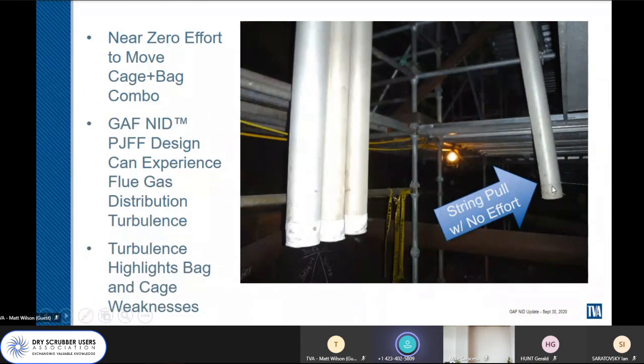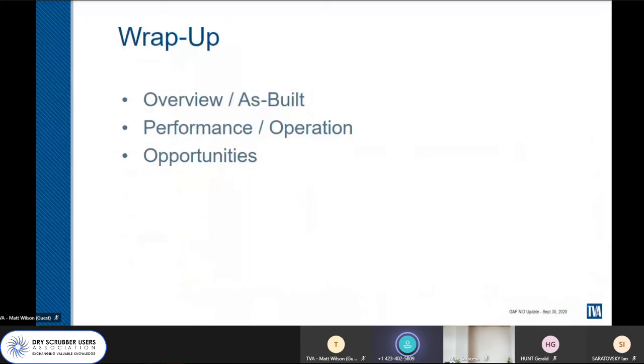So I had done this, I attached a string, and with essentially no effort whatsoever, was able to pull this a good clear 6 feet away. So what we're getting at there is it does not take much to move around a 10-meter length bag and cage combination. So we have experienced some issues with that. That's a whole other presentation on our bag house experience. But long story short, a NID design bag house can experience flue gas distribution turbulence. And our recommendation is to scrutinize CFD analysis of both particles and flue gas flow and direction and velocity inside the bag house itself. And so we've gone over overview, as built, performance, operation, and some opportunities.